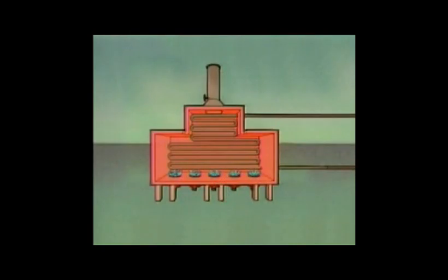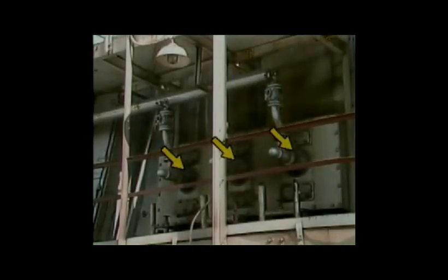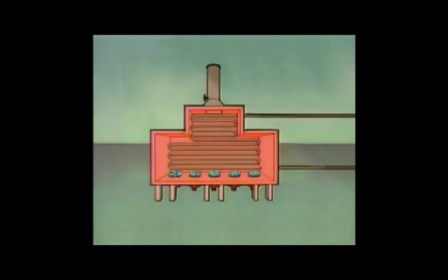Let's take a look at a typical furnace. This one consists primarily of a large box or shell and a stack. During operation, heat is produced by combustion inside the shell. The exhaust gases are routed to the atmosphere through the stack. The heat is provided by burners located in the floor of the shell — this type is a floor-fired furnace. Some furnaces are wall-fired, while others may use both wall and floor burners. In addition to burners, furnaces contain many other important parts.